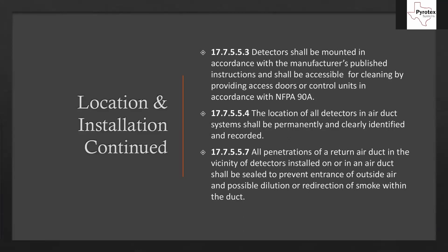A few more code requirements for duct detectors: detectors shall be mounted in accordance with the manufacturer's published instructions and shall be accessible for cleaning, by providing access doors or control units in accordance with NFPA 90A. We must ensure duct detectors are somewhere accessible — if it's a sheetrock ceiling, we may need to coordinate placement of an access hatch so the unit can be serviced.